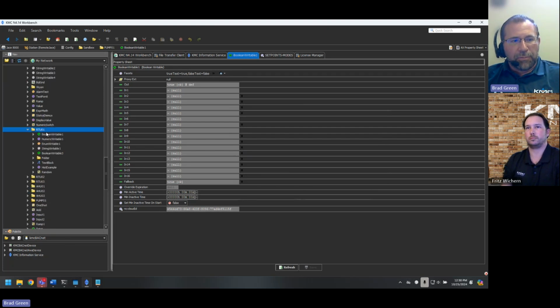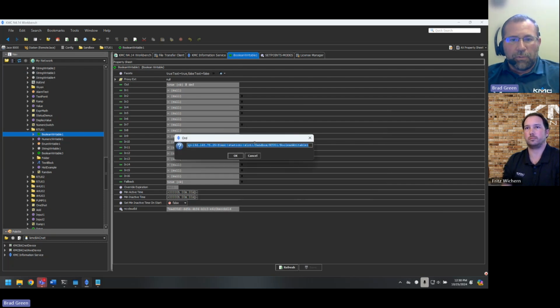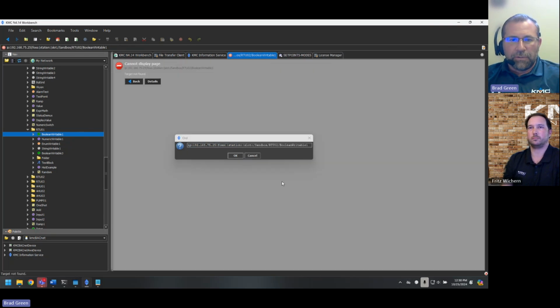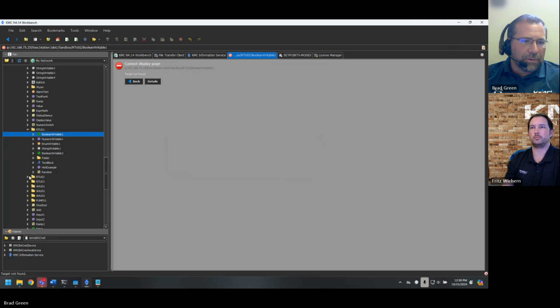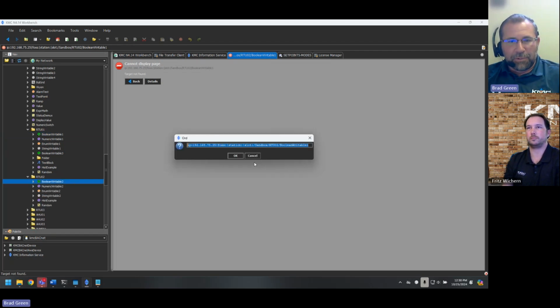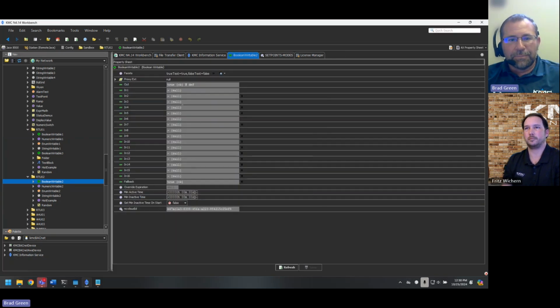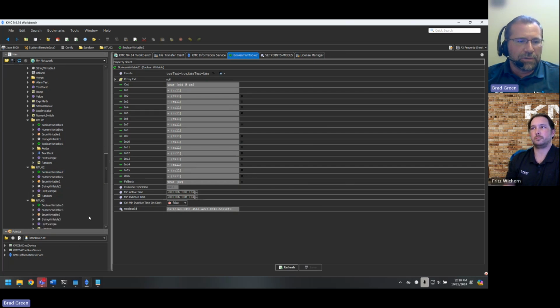Also, if you have common profile types, so if I'm in this Boolean writable 1, if I hit Control and L or do my open ord, then I can go quickly. I can just edit this manually, so I know I want to go to number 2. Oh, it's called 2 here, so I guess it would work if you had the same name. But there we go. So you can manually edit those ords and jump between things, which is kind of helpful, especially if you have VAV boxes, you want to change the set point on all of them.